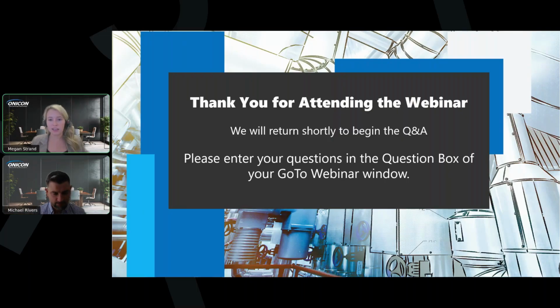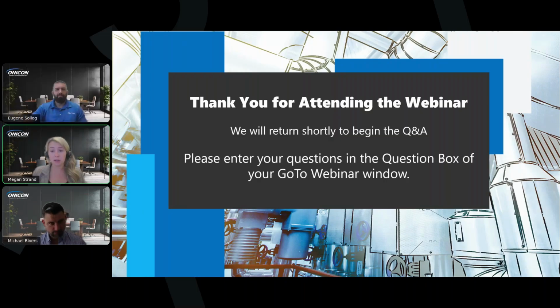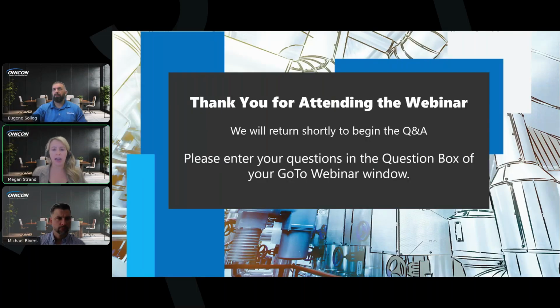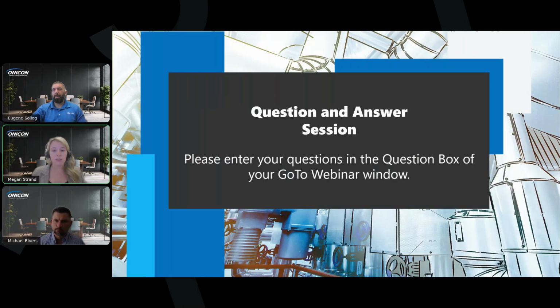Yeah, I can go ahead and answer that. It's a good question. Maintenance on the FT3000 series is pretty minimal. There are no moving parts within the flow sensor, so you can expect years of reliable service with very little maintenance. One thing I do want to highlight is that for dirty water applications, the transmitter does have the capability to clean the electrodes.